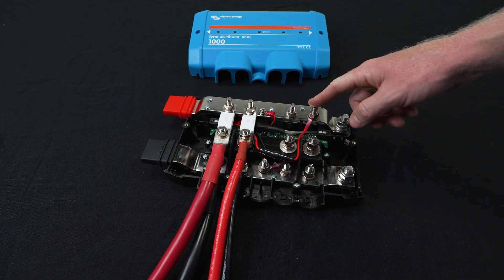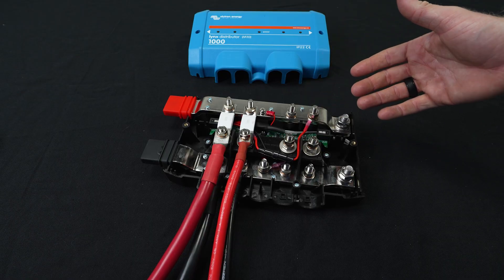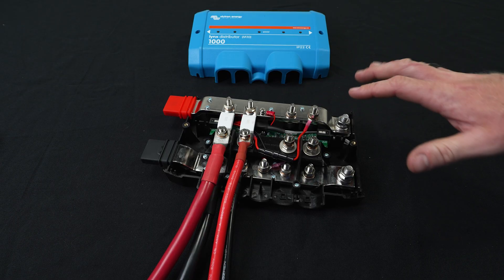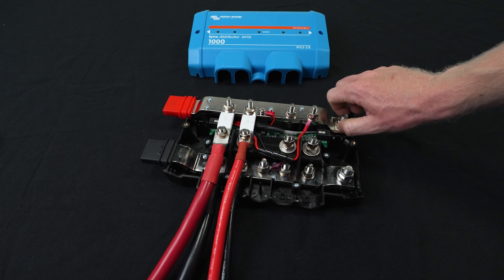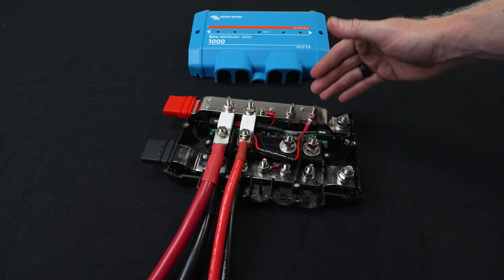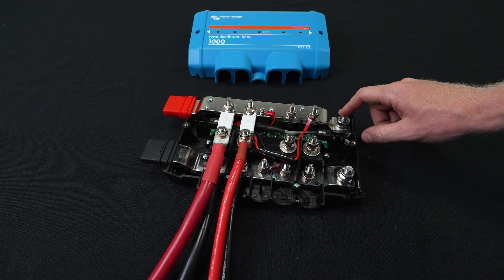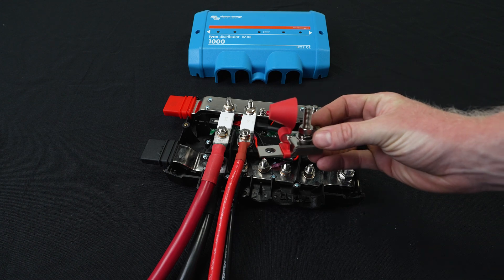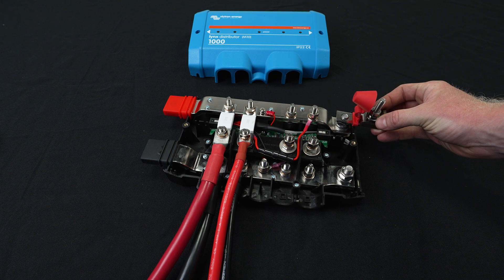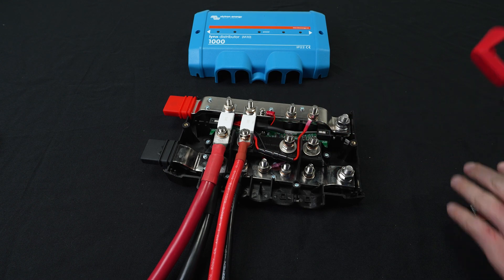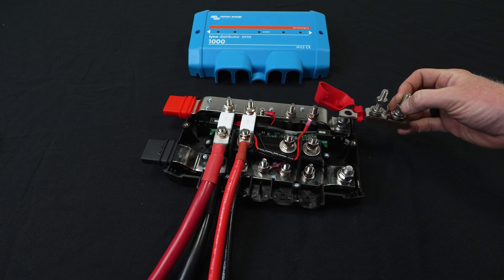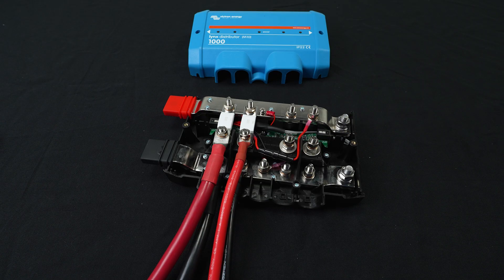Whereas on the positive, you want to make sure each connection is individually fused with a few exceptions. So to do that, to add an extra slot for a positive, we can actually land an MRBF holder on this post here. There's even the option to add a dual post MRBF holder. And then we would add two fused circuits to the right side of the Lynx distributor. So we're going to show you how to do that.